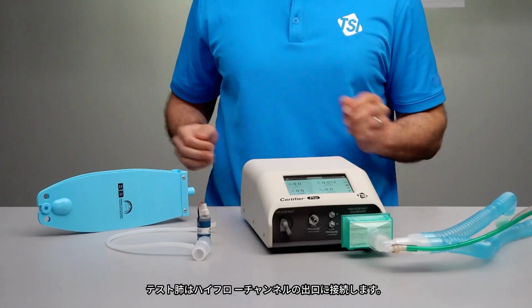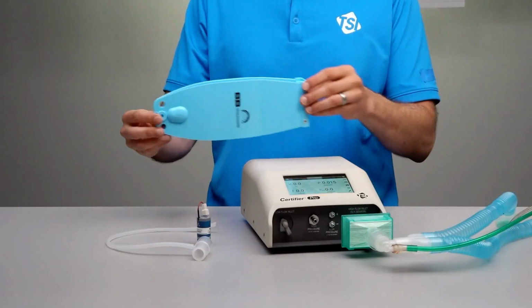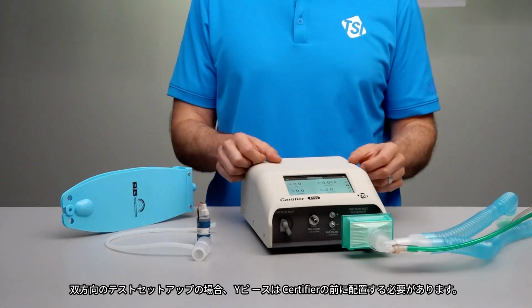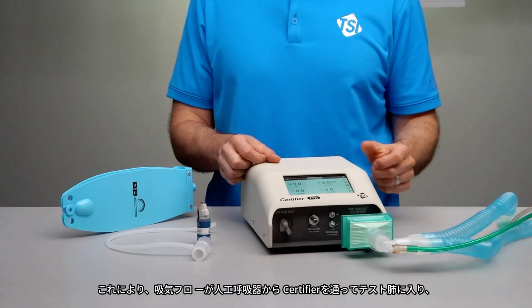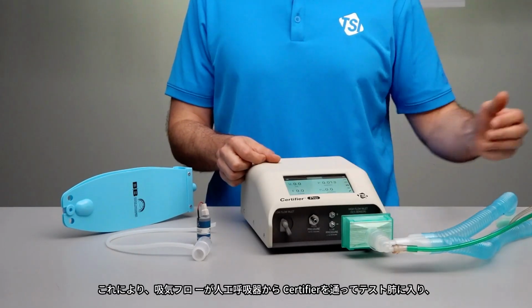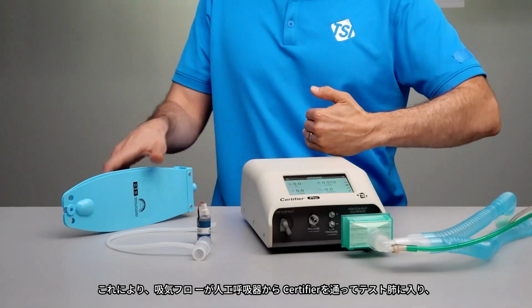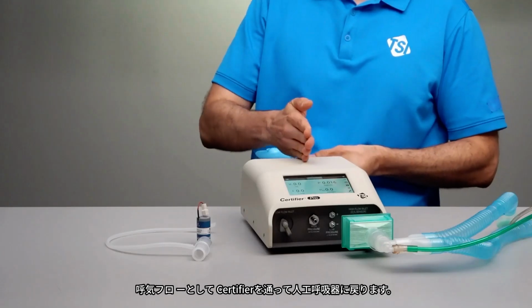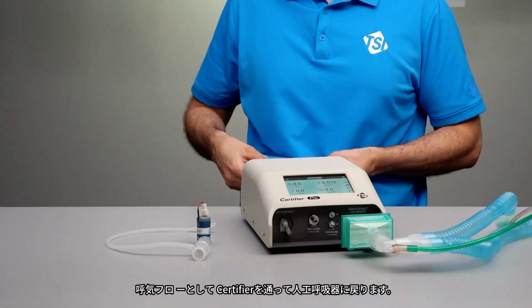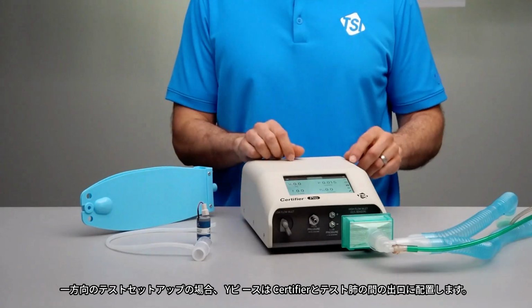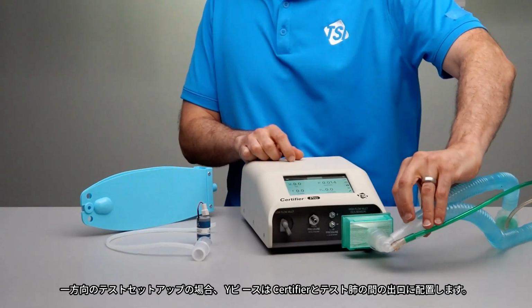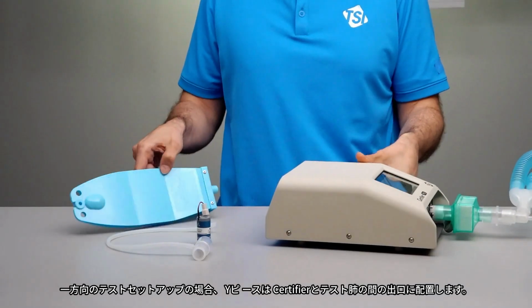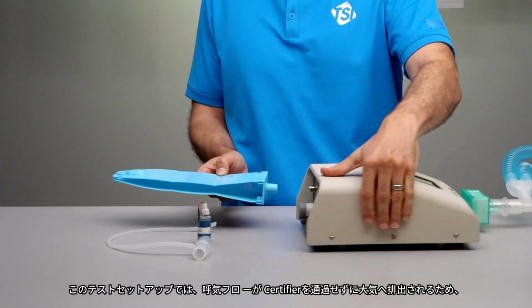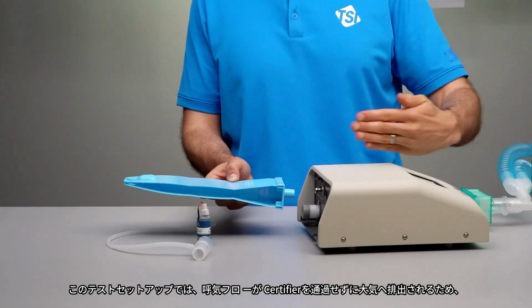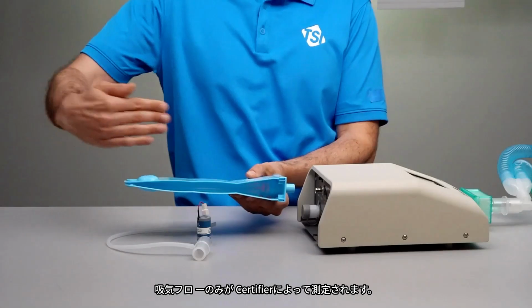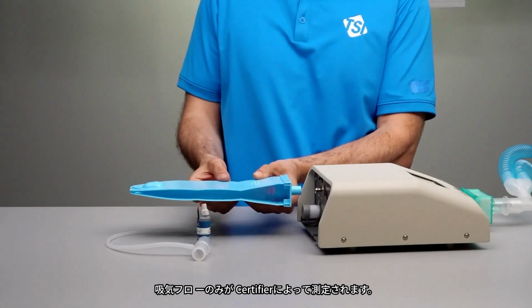A test lung will be connected to the outlet of the high flow channel. For a bidirectional test setup, the Y fitting needs to be placed before the certifier so that inspiratory flows come from the ventilator through the certifier into the test lung, then back through the certifier as expiratory flows, which then return to the ventilator. For a unidirectional test setup, the Y fitting would be placed in the outlet between the certifier and the test lung. With this test setup, only the inspiratory flows would be measured by the certifier, and the expiratory flows would be diverted from passing through the certifier and instead vent to the atmosphere.